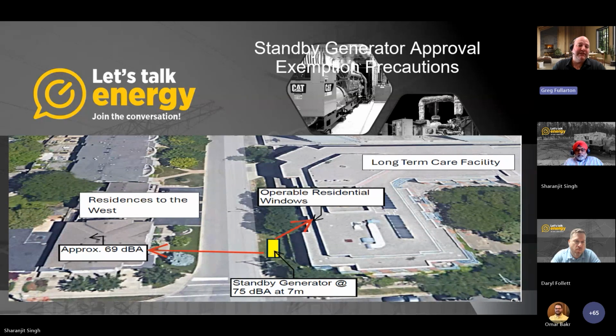Now, the sound level limit criteria for that is 55 decibels. And that also depends on what the municipal noise bylaws state as well. So is that showing compliance? No, it's not showing compliance with the provincial noise guidelines, and it may not be showing compliance with the municipal noise criteria, typically not. So that is, first off, not the best location to install that generator. When we do an environmental compliance assessment, we kind of phase those out and work with the client to do the best they can. They can certainly put the generator there and hope nobody complains. But once you install it there and then there's a complaint, sky's the limit to repair.